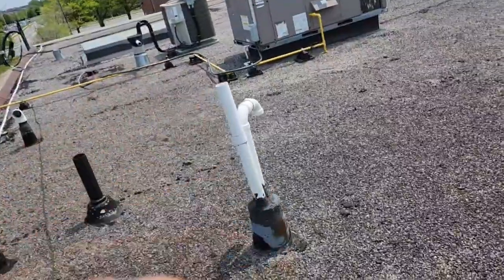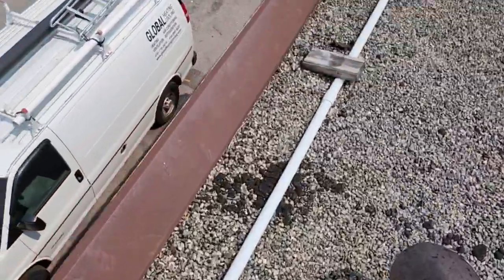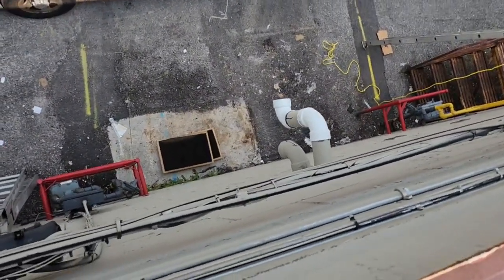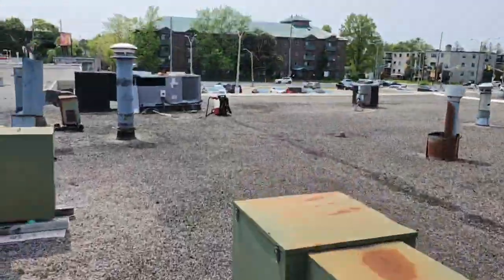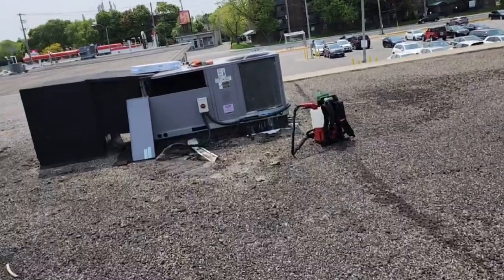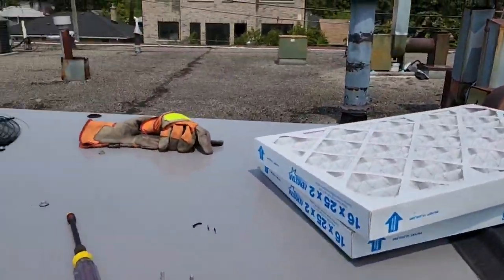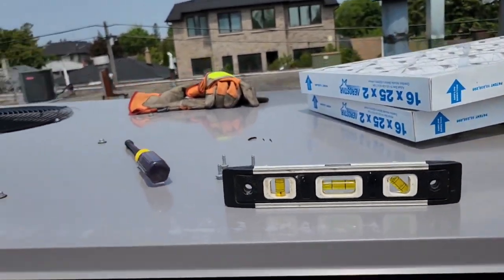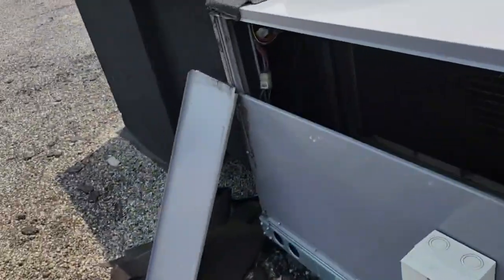This guy got my number, so he asked me to come work on that one, but not today. See the filters right there — they're literally clogged, really bad. Anyway, that's an interesting installation. The unit is not level — I purposely brought the level to show it on the video. They shouldn't be installing it like this. Really poor install. Oh my god, it's terrible. But anyway, it is what it is. I see weird things every day and this is another one.